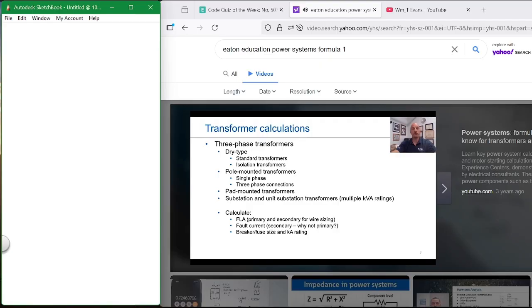Now what we're going to do is go through and calculate full load amps on the primary and secondary of a transformer, the fault current on the secondary, and also the breaker or fuse size and the kA rating of those breakers. We're going to talk about how that comes into play here.